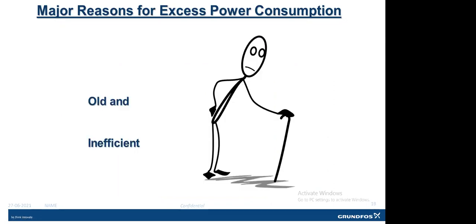Another common reason is old and inefficient pumps. At many facilities, there are pumps which are more than 10 or 15 years old. Over a period of time, due to technology enhancement and modifications, energy-efficient pumps have been developed which are more efficient than the older designs. In common practice, take the example of our car or bike, which used to give lower mileage in the year 2000; now if we consider that same brand, we are getting more mileage. The same applies here as well. Due to technology enhancement, the efficiency increases for that design condition.